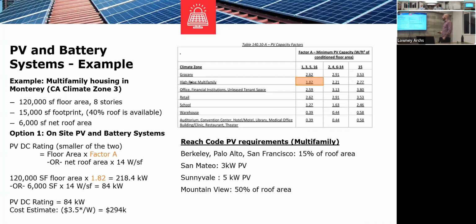So here's an example. I picked an 8-story multifamily housing building in climate zone 3. I just picked Monterey for this example, but Oakland and San Francisco are also in climate zone 3, so it'll be the same. This building has a 120,000 square feet floor area. It's 8 stories, and I assume it would be just a boxy, rectangular prism building with a uniform floor area per floor. So that gives me 15,000 square foot of footprint for the building.